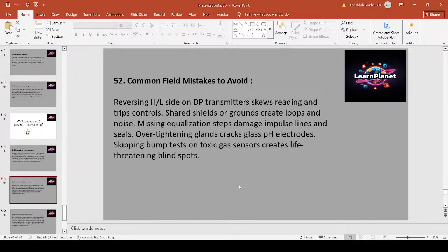Common field mistakes to avoid. Reversing H/L sides on a DP transmitter skews the reading and trips controls. Shared shields or grounds create loops and noise. Missing equalization steps damage impulse lines and seals. Over-tightening the glands cracks glass pH electrodes. Skipping bump tests on toxic gas sensors creates life-threatening blind spots.